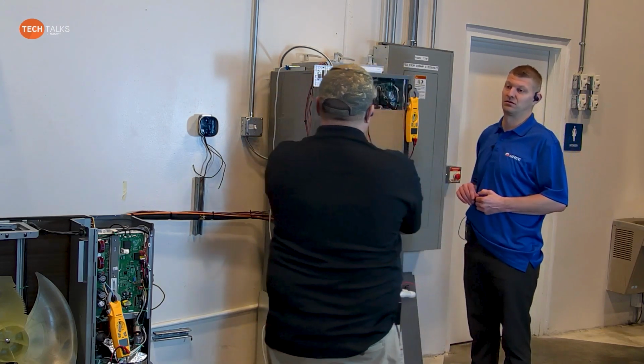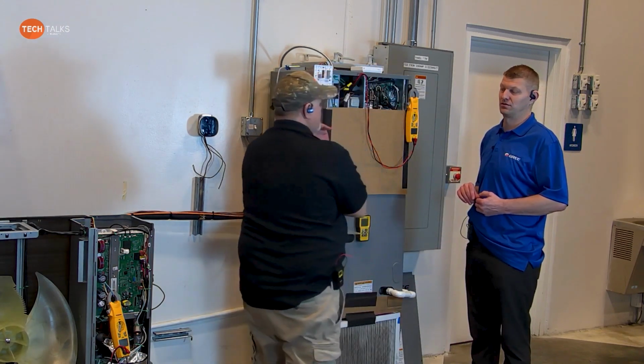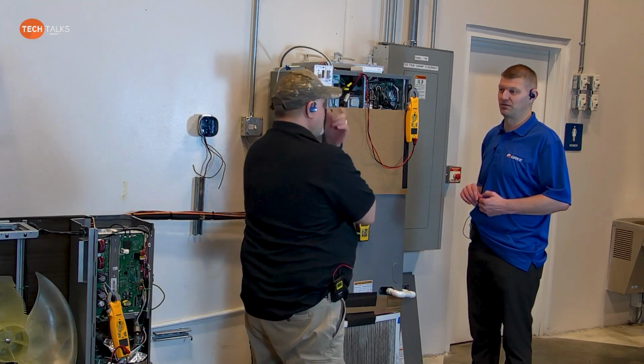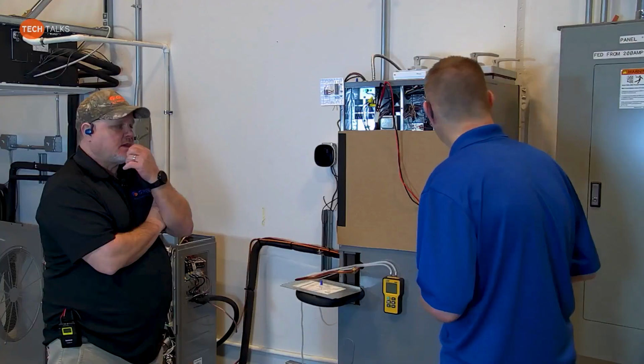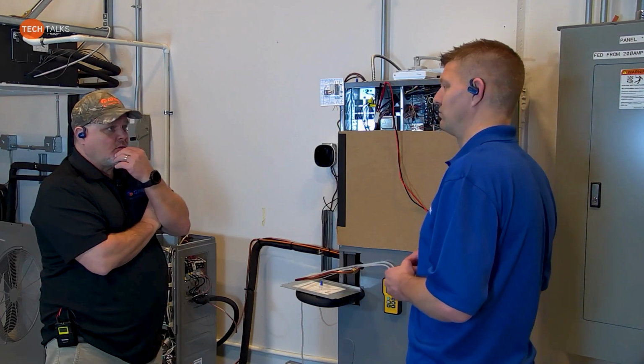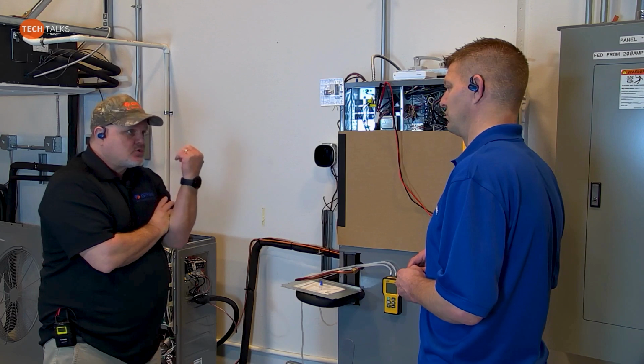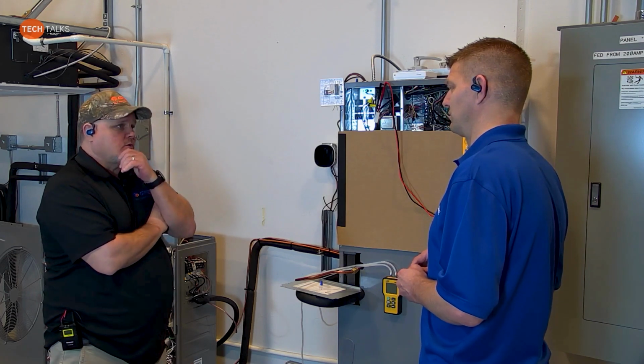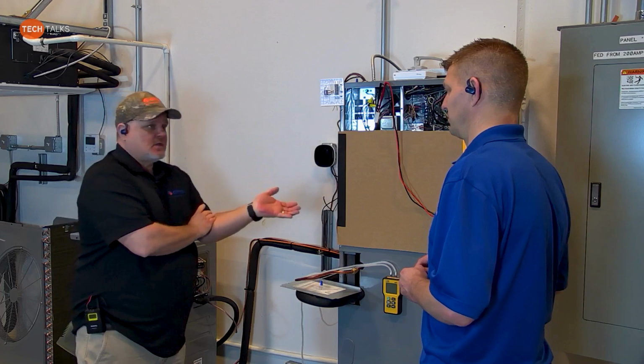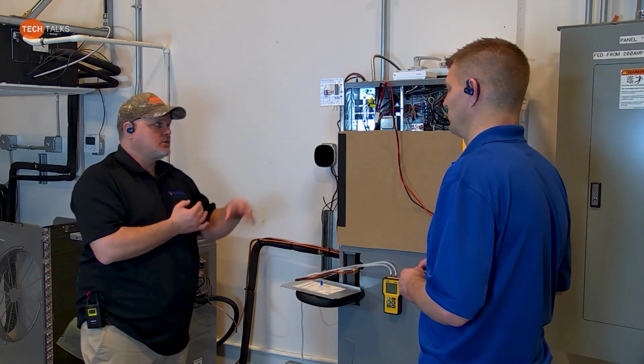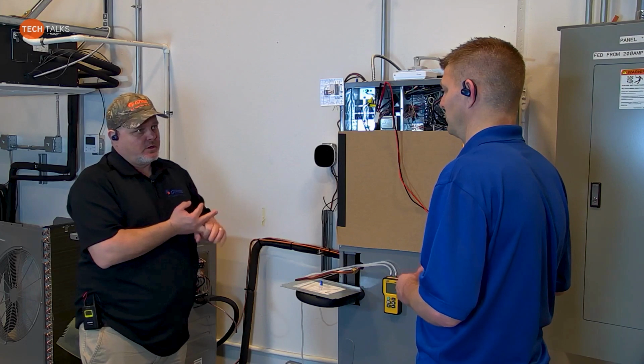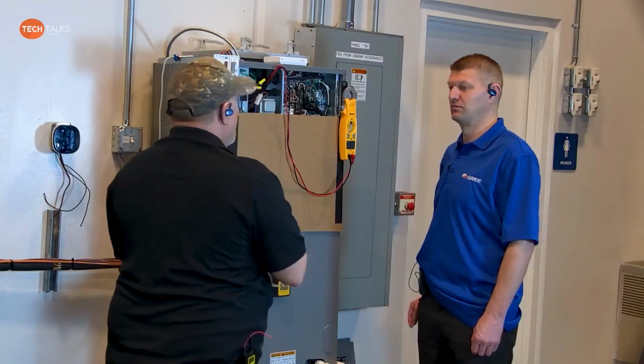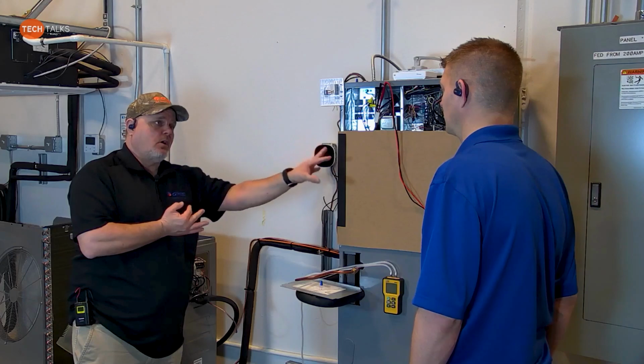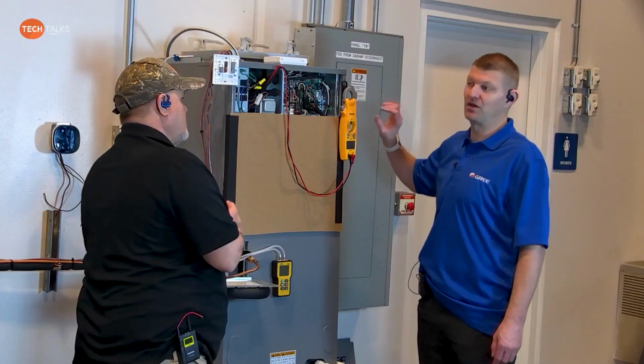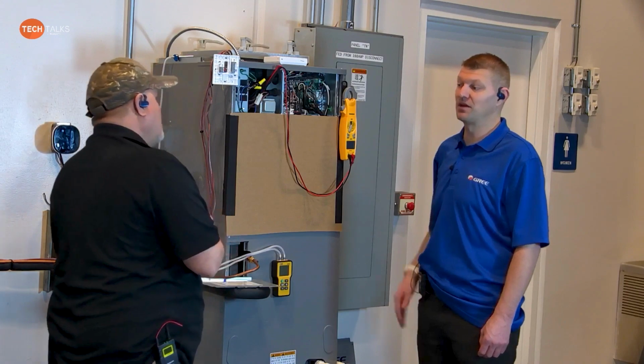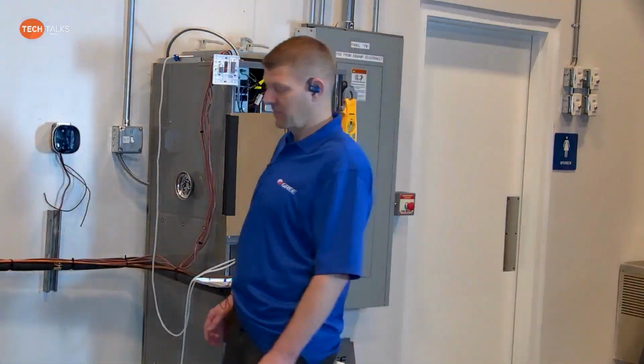Yes. So in the previous FLEXX, we never adjusted the cooling dip switches. We only adjusted the heating dip switches. Correct. Right? Yep. And the same thing's going to happen here. I believe we're only setting the heating dip switches for airflow, but now we are going to use that other switch bank, which we didn't use in the 410A version, strictly for setting this thing up for whether we want RS485 operation using the GREE controller, or whether we want it to be 24 volt. Right. Correct? Okay. So for 24 volt, does that switch in there need to be on or off? For 24 volts, the SA1 number 1 dip switch needs to be on. Needs to be on. Okay. Yep. And same thing for the outdoor unit. So the outdoor unit, is that an SA1 dip switch as well?